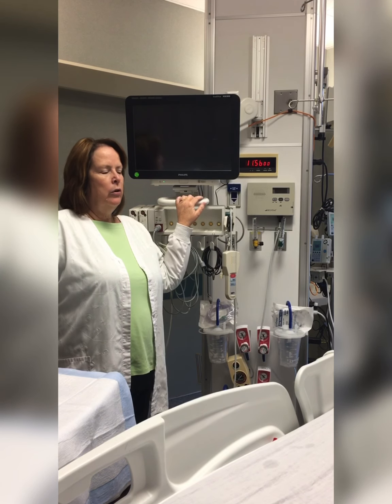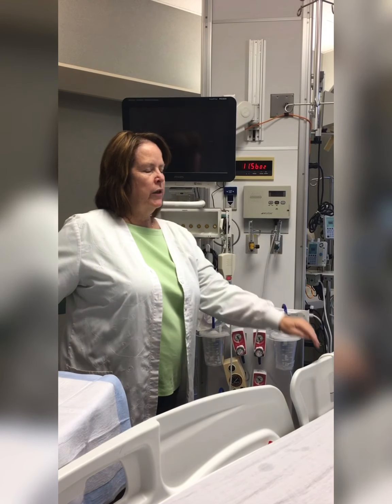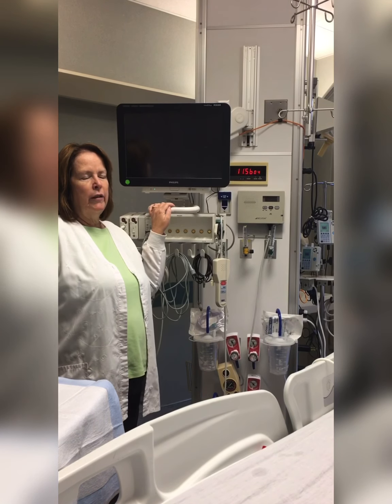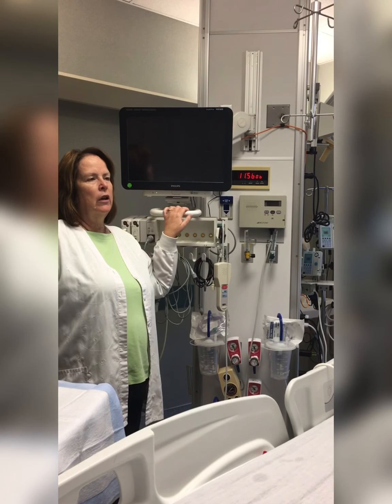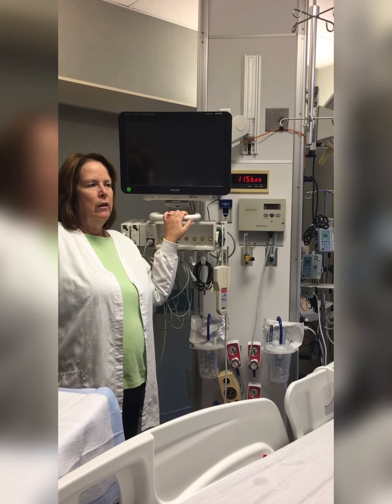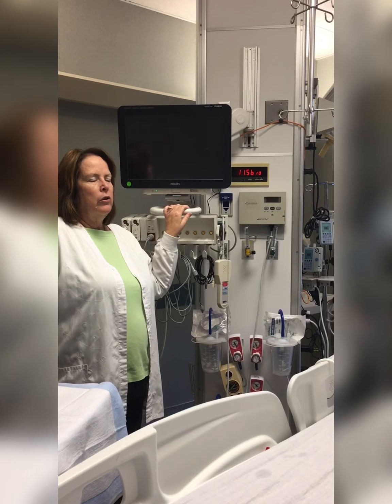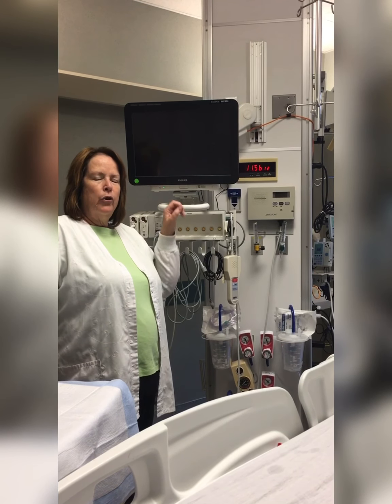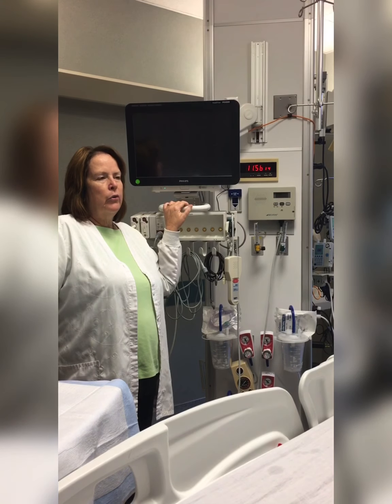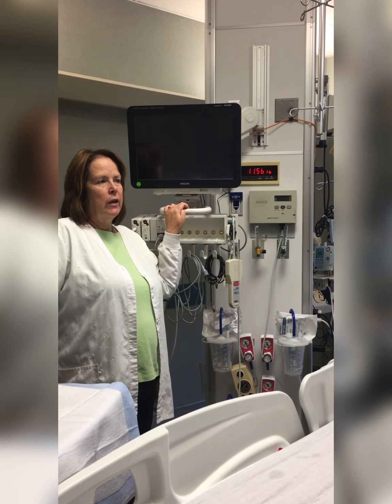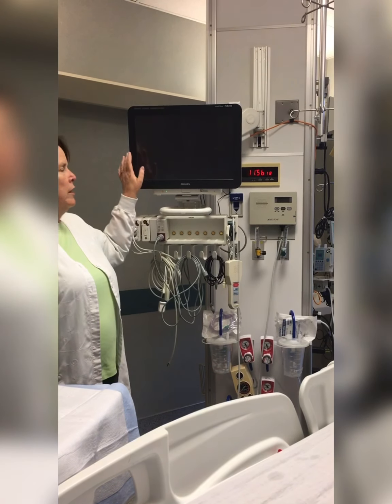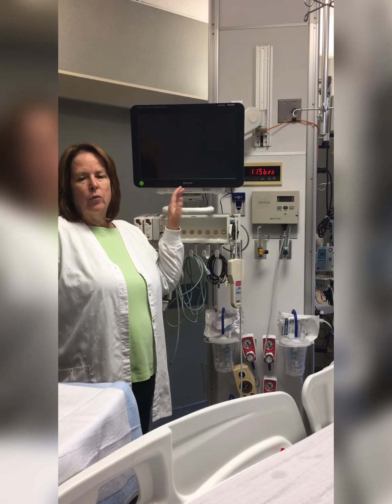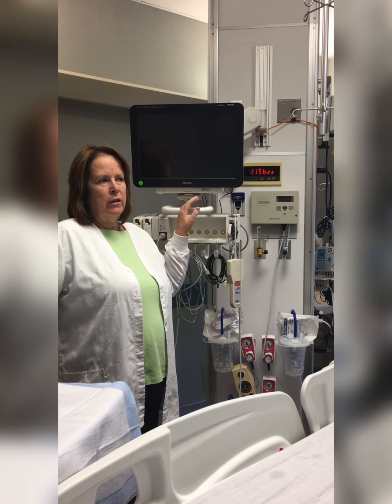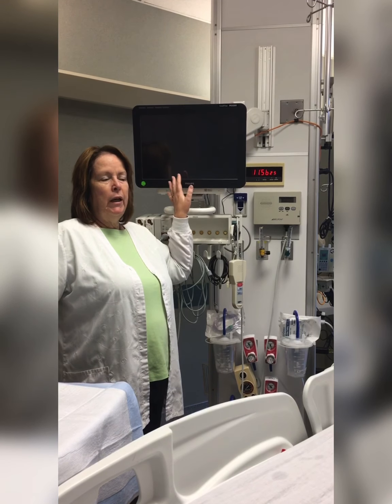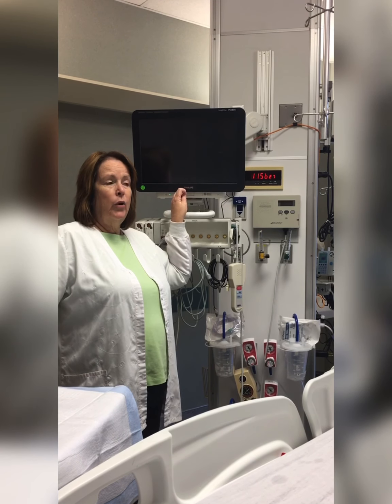You're going to zero the transducer at the right atrial or the left atrial site, just like you do your art line, like you do your CVP. And then when you need to check your catheter for your measurement, do it two or three times a day to make sure your measurement is correct. When you look at your monitor, it will have a PA reading when the Swan-Ganz is at rest. Every time you look up, it should have PA. It shouldn't have anything that looks like a wedge pressure.